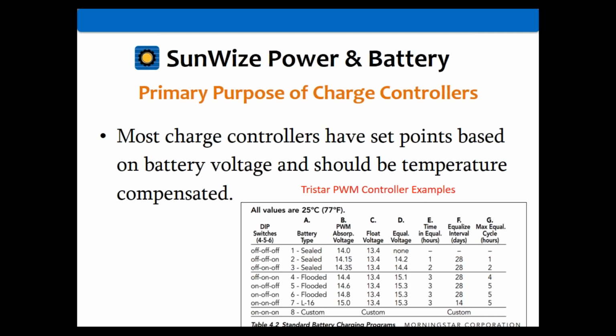As an example, here's the TriStar PWM chart. They use dip switches, which we're going to get into in detail with regards to adjustable set points. You can see they have 7 different standard settings, plus one for custom settings, in case those voltages don't match what you need for your charging.